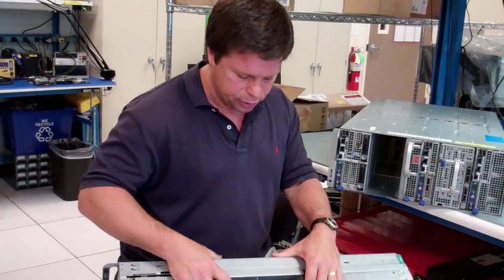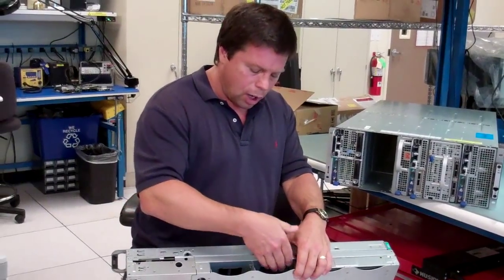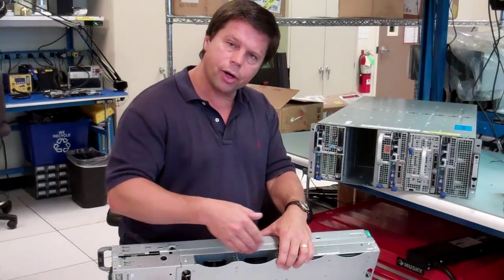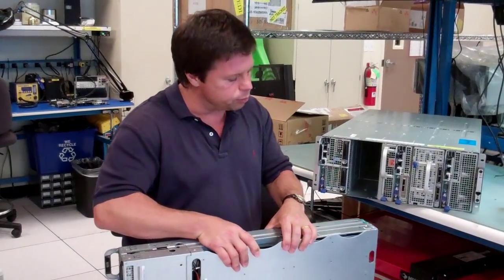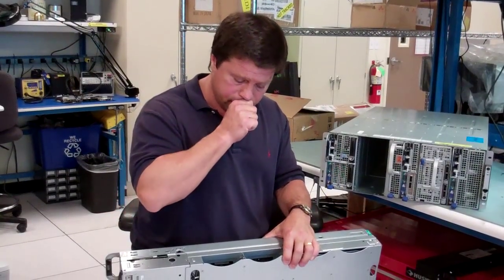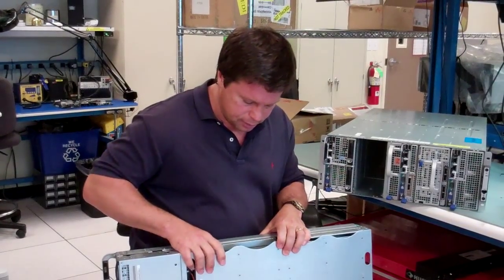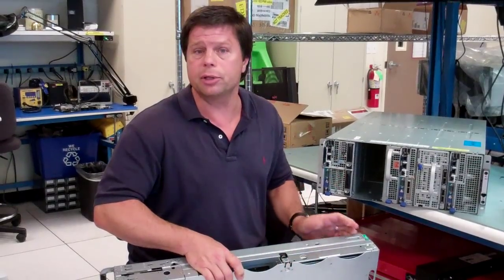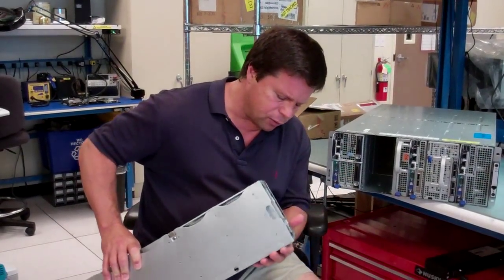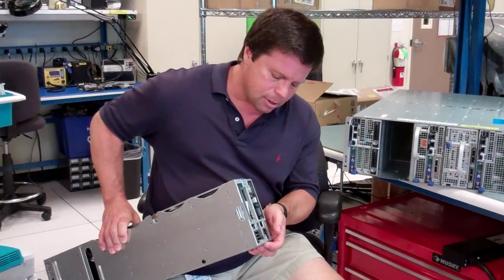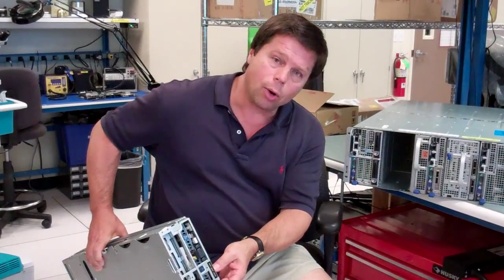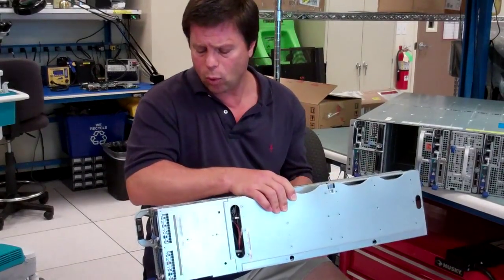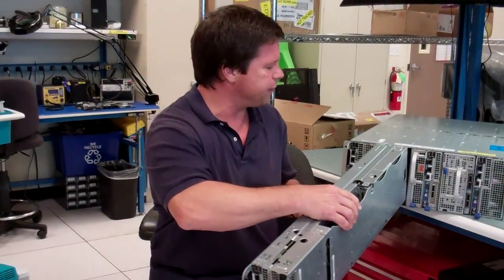You have, since you're now in a wider space, you can add in additional PCIe card, and these would be the cutouts for the PCIe card bracket. You also have the ability to put in drives that are not hot-pluggable, yet they're in a very simple carrier such that you can very quickly swap them out once you pull the sled out and disengage it, as opposed to needing to unscrew a bunch of screws and disconnecting cables. Those drives leverage kind of a quick disconnect backplane style of connection, but again, they're not hot-pluggable in that the sled is out, so obviously the power is not applied to the sled, but very quick service. And then you still have in the back the two buried 2½-inch drives. And then, like all the other sleds, you make that power and control connection back into that midplane. So this is a double-wide compute with two front hot-plug 2½-inch drives.